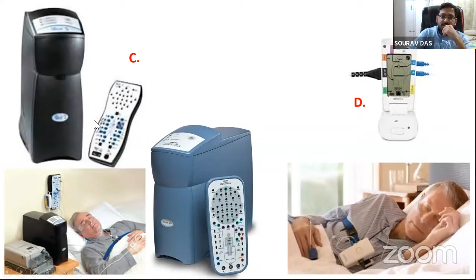But the general models at least have the airflow, the oxygen saturation and desaturation, the pulse rate, and the abdominal or thoracic effort. That is how much effort is being put into the respiration. Now, this is the level 1 device. Actually, this device can be used for both level 1 and level 2.